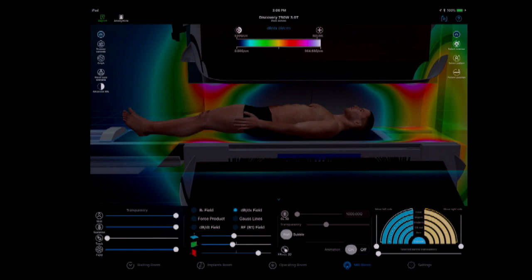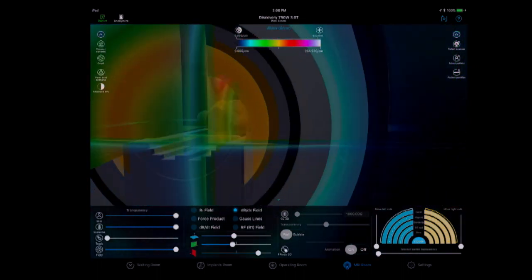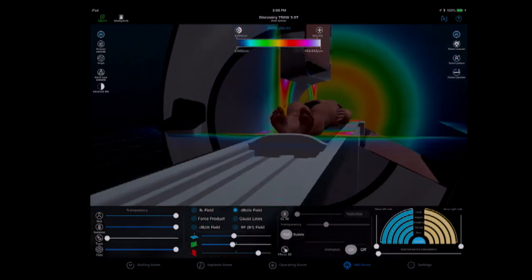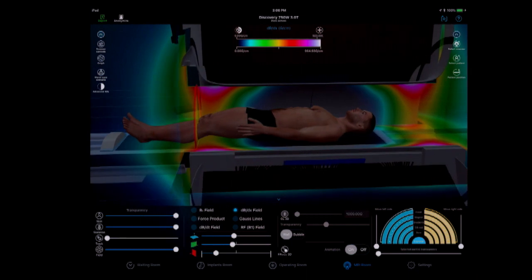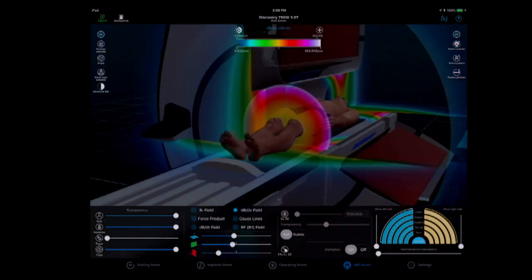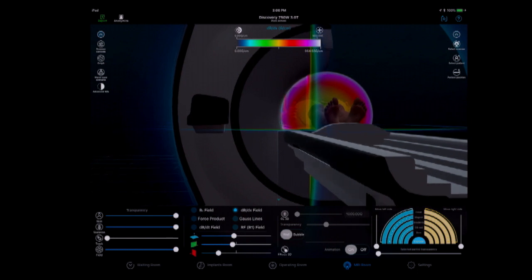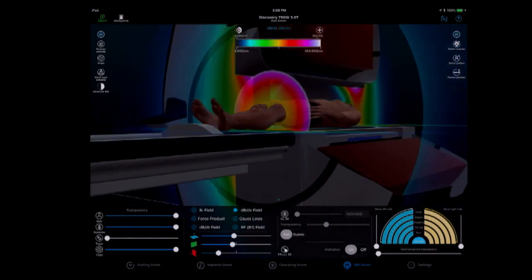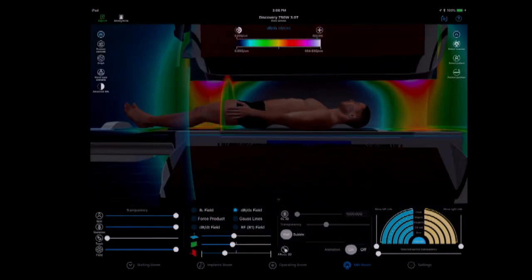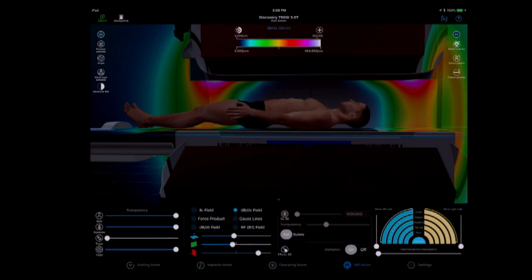This is what it's like for B0. This is what it looks like for dBdx. Let's bring this guy in and show it to you this way as well. Can you see it? Even looking down the bore, notice how much weaker it is at the center than it is at the periphery. Does everyone understand that? And exactly as he said, in the center there's almost no dBdx because the center is where it's homogeneous.